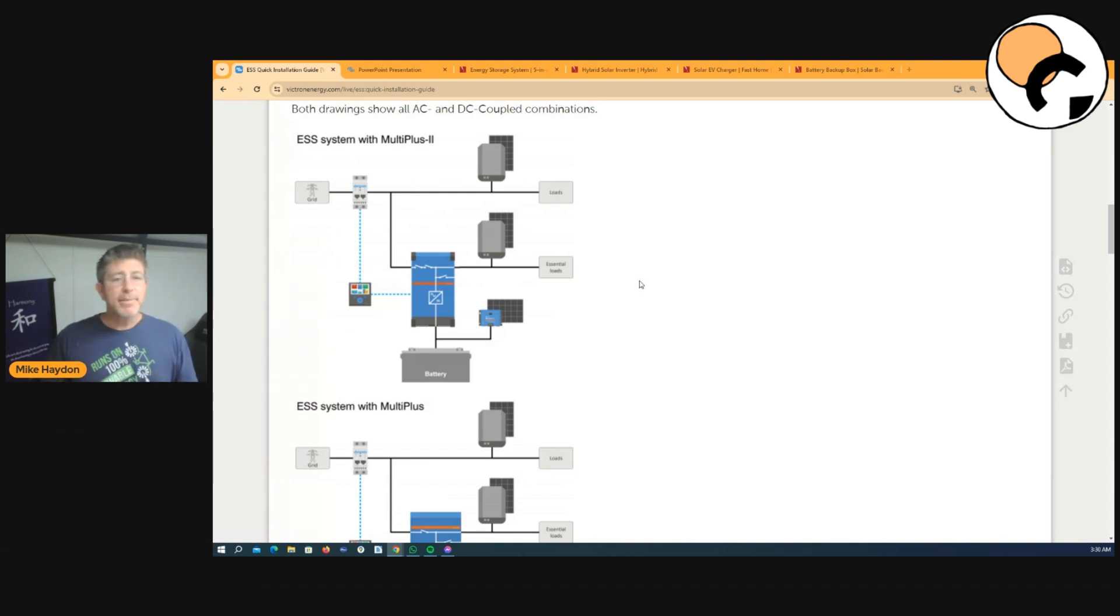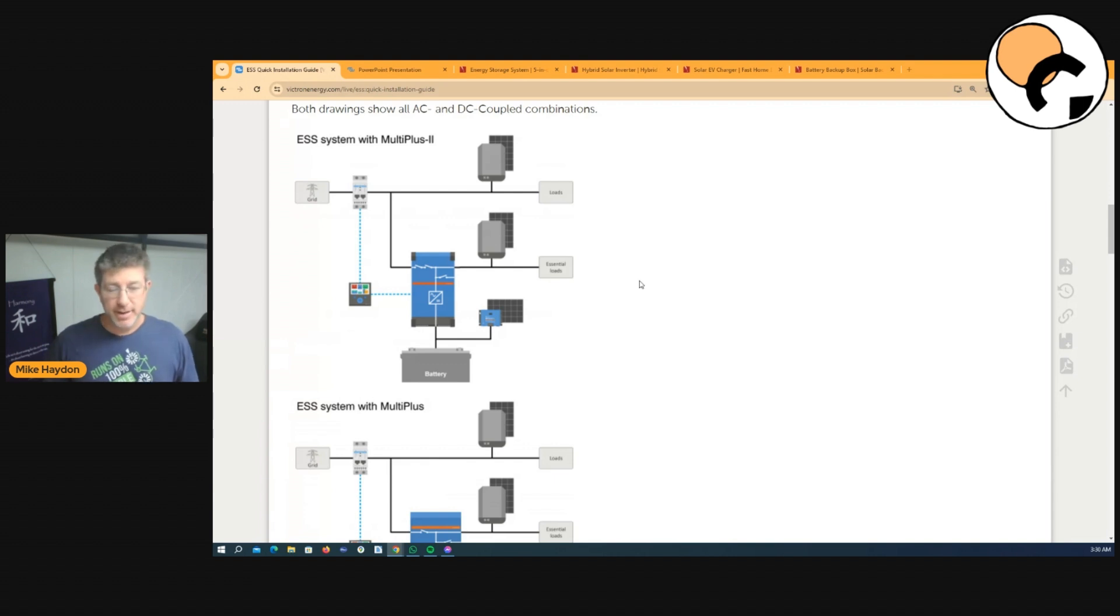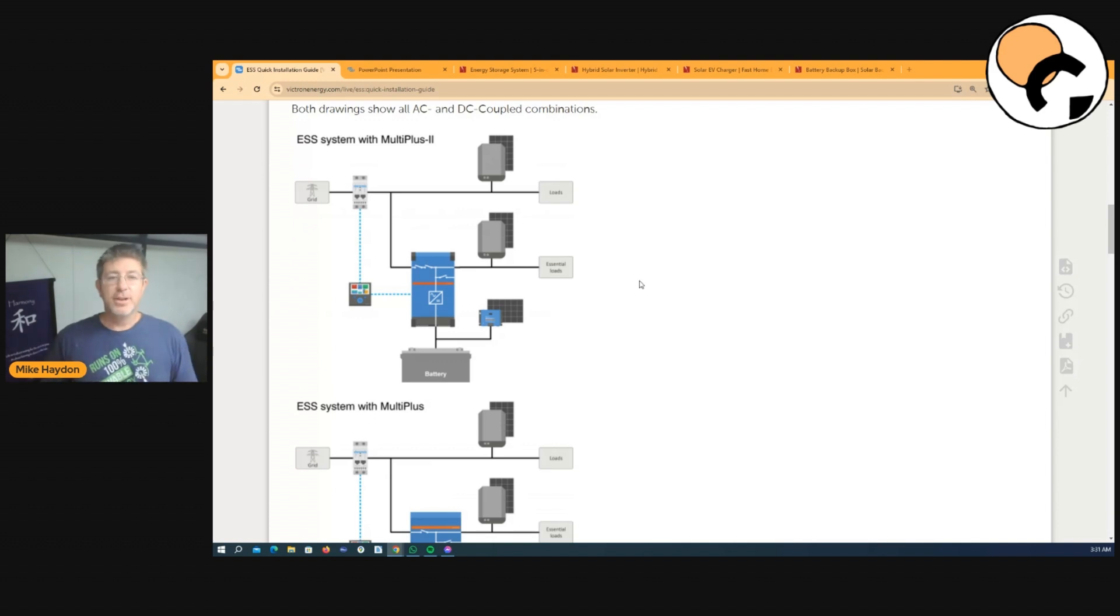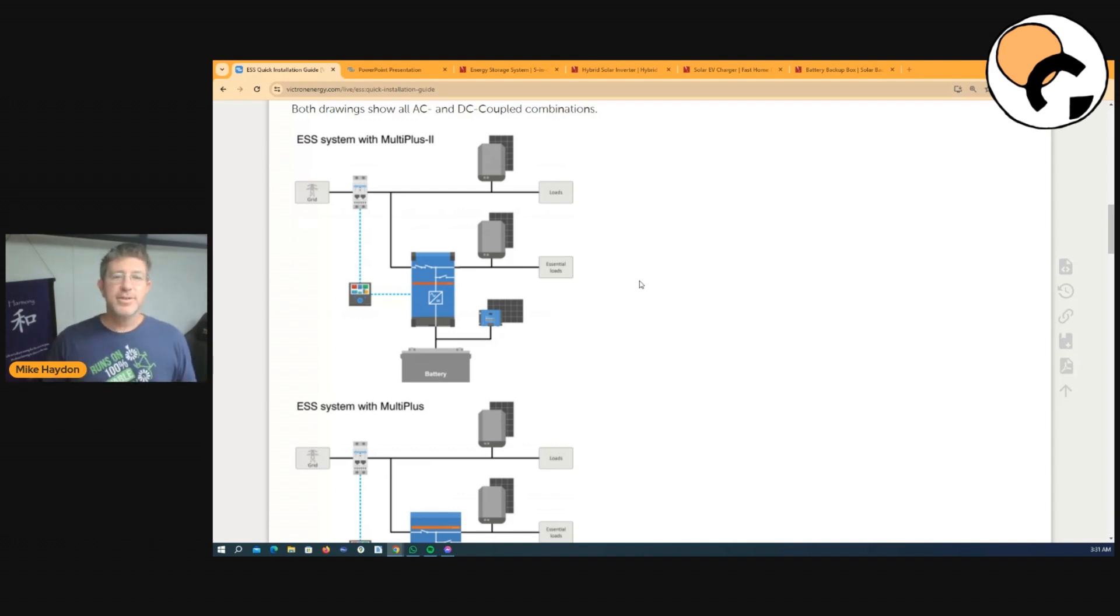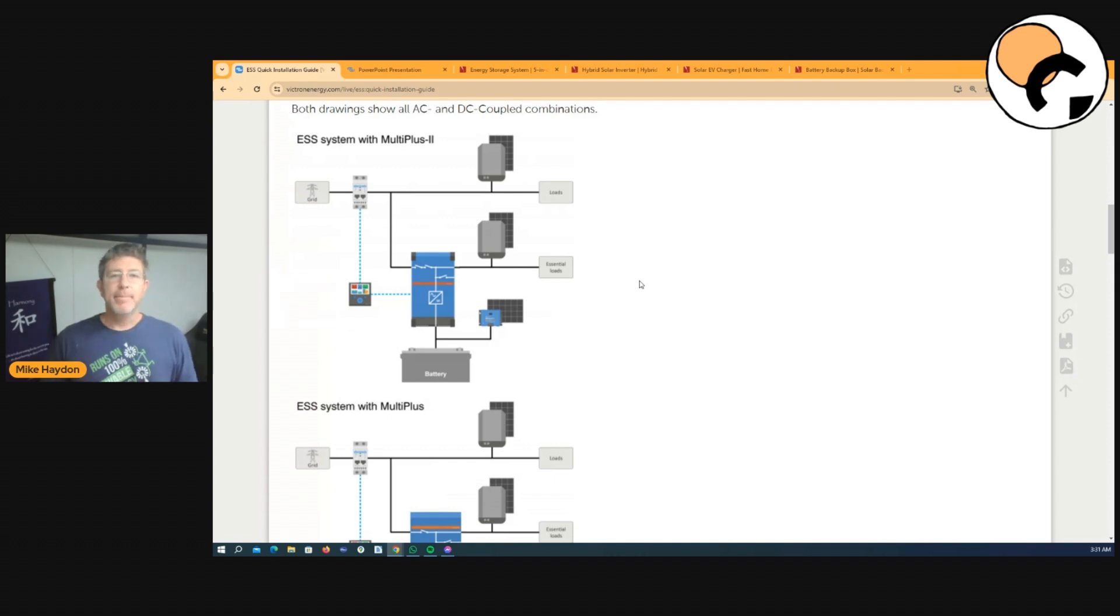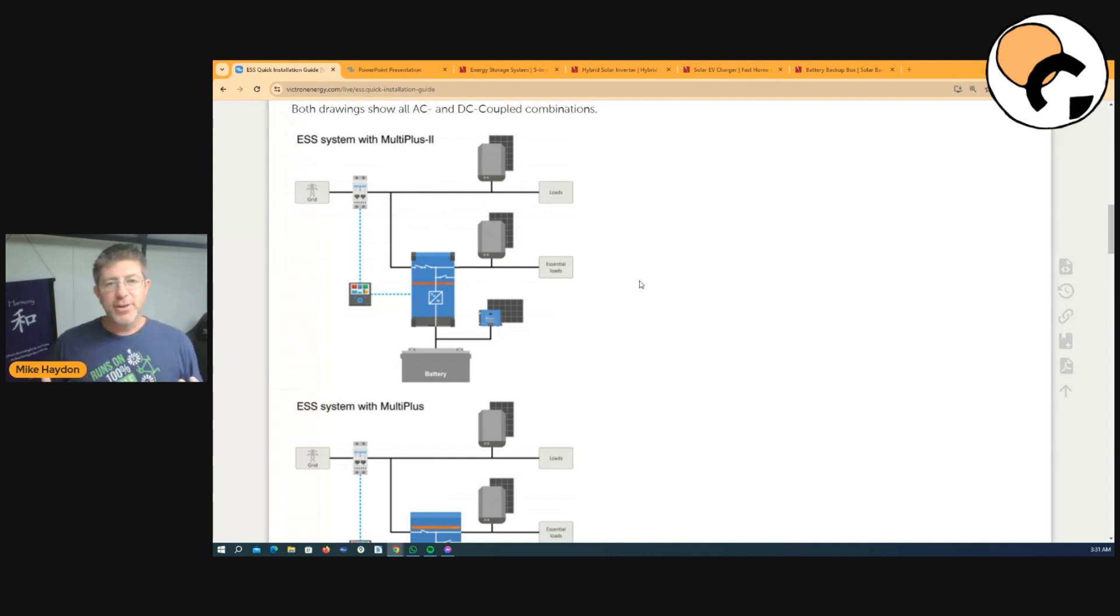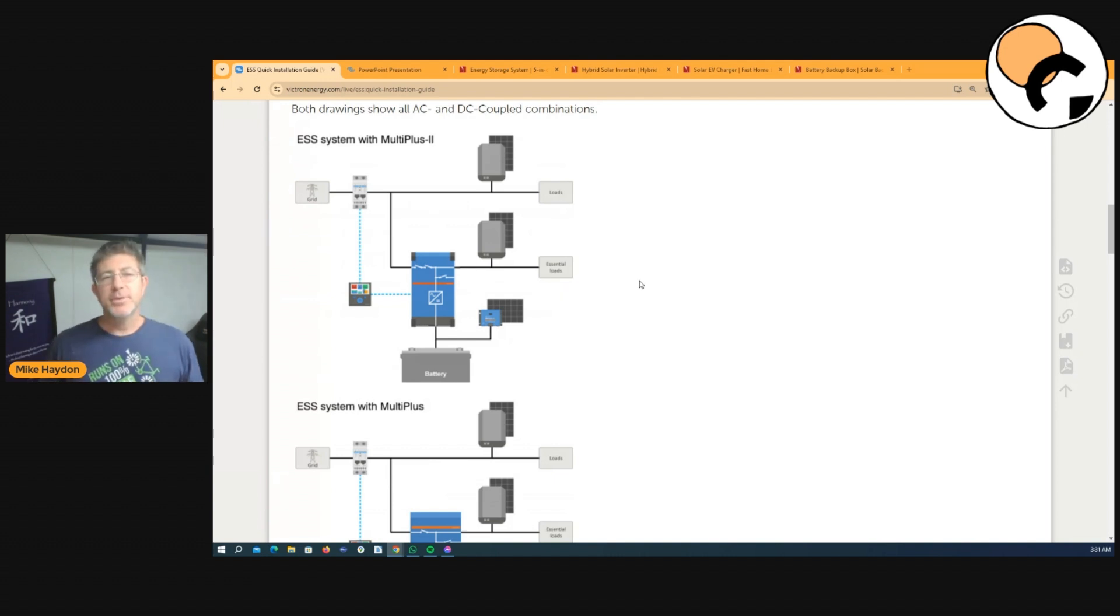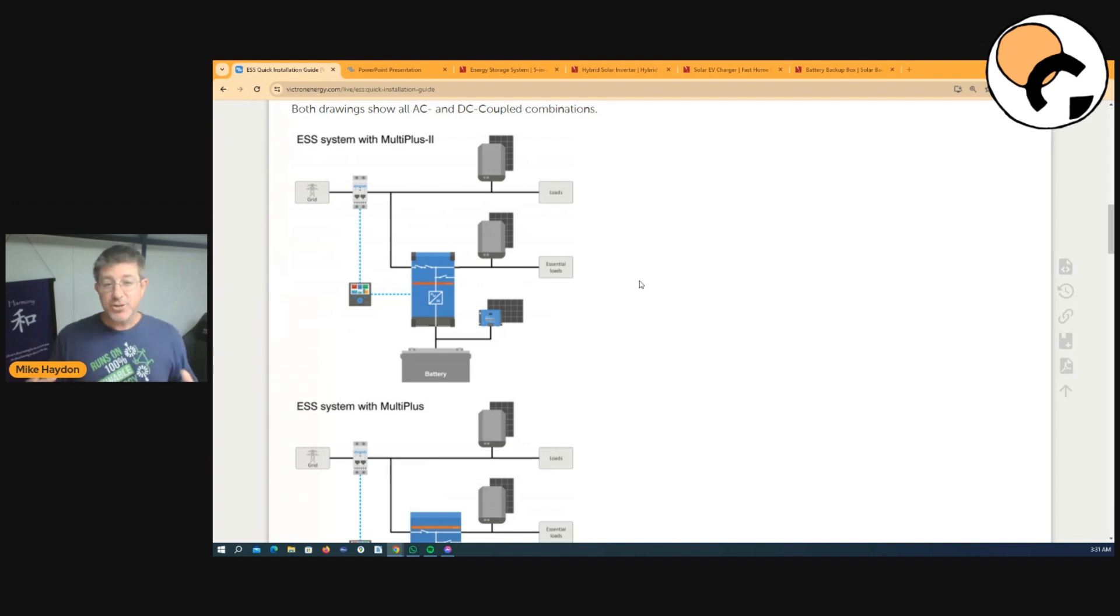And the same thing as well, if one of those inverters fail, you still don't have a backup for single phase. And then you could have two inverters on each phase. So you'd have six inverters in total on the three-phase system. And still, if one of those inverters fail, the system requires reprogramming back to be able to work in your situation to give you power. So that can be very complicated. And also, it's not very nice. It's stressful to do when there's a blackout situation. It's always when it's raining. So this can be a really unreliable system. And this is not just picking on Victron in general. It's just the way the industry has actually designed systems.